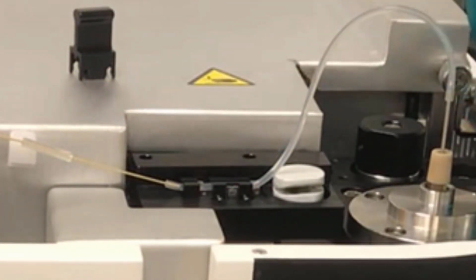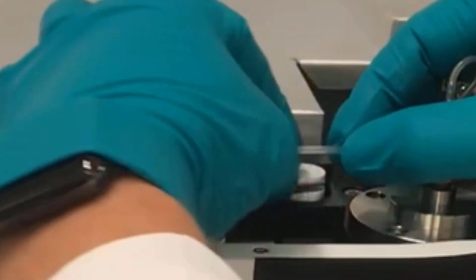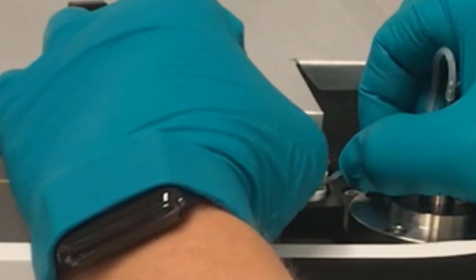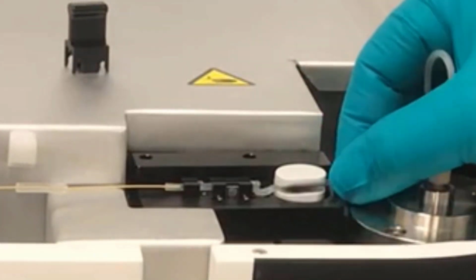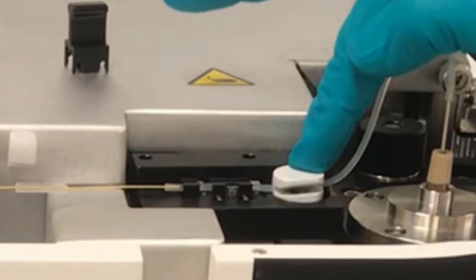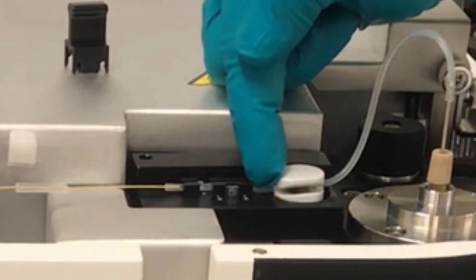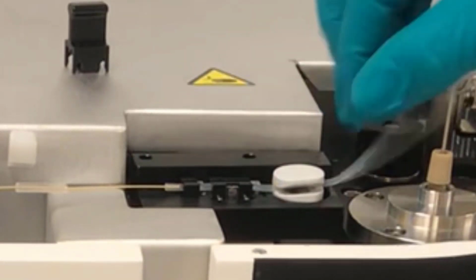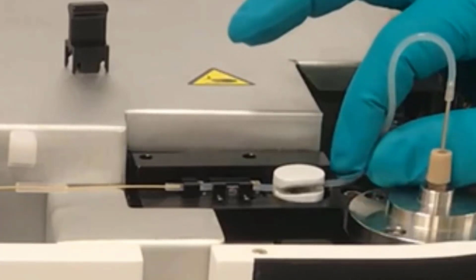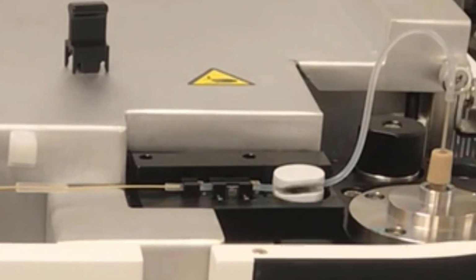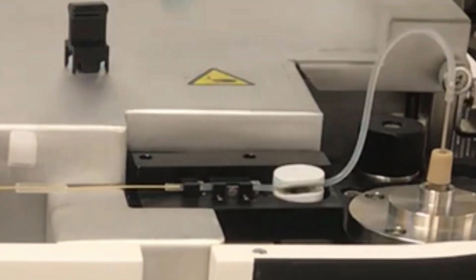Push the silicone tubing into the pinch valve slot. Ensure that the tubing is completely seated to the bottom of the slot so that the pinch valve functions properly. Check for and remove any kinks in the tubing. You can pull the sample line until you have a straight line. Reinstall the sample line bubble detector cap.